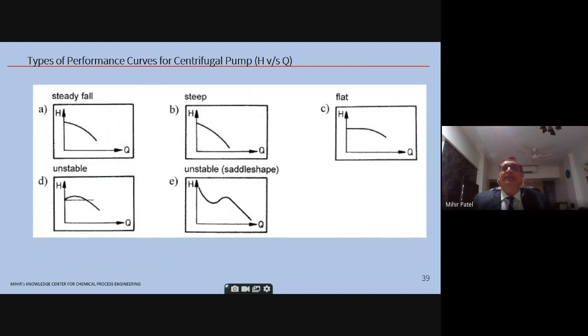Usually, good engineering practice dictates that shutoff head should not be more than 20% over the design point. You don't want a very steep curve as in the B category, and the pump should rise in a flat manner towards shutoff. So this pump is the best out of the whole lot, because it has a falling curve, but not very steep. These are the things one should remember: performance curves, head versus flow rate.